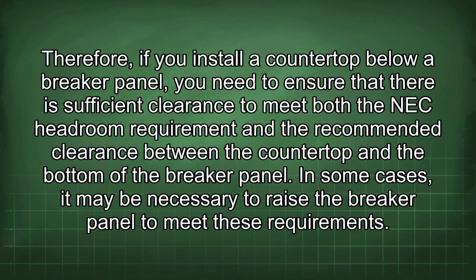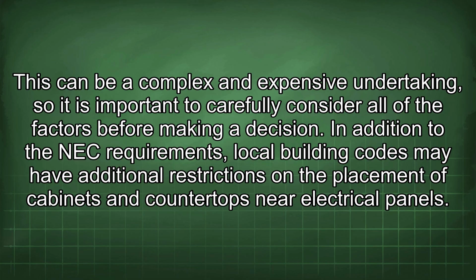Therefore, if you install a countertop below a breaker panel, you need to ensure that there is sufficient clearance to meet both the NEC headroom requirement and the recommended clearance between the countertop and the bottom of the breaker panel. In some cases, it may be necessary to raise the breaker panel to meet these requirements.